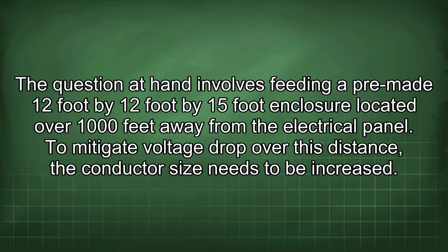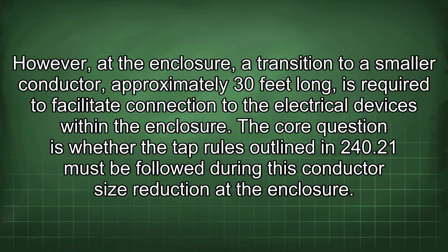The question at hand involves feeding a pre-made 12-foot by 12-foot by 15-foot enclosure located over 1,000 feet away from the electrical panel. To mitigate voltage drop over this distance, the conductor size needs to be increased. However, at the enclosure, a transition to a smaller conductor, approximately 30 feet long, is required to facilitate connection to the electrical devices within the enclosure.